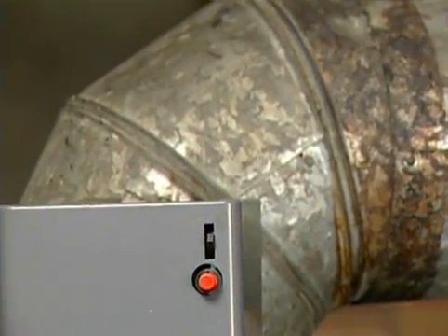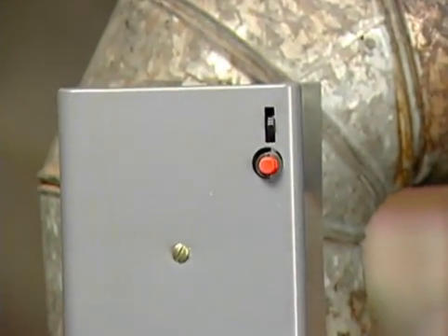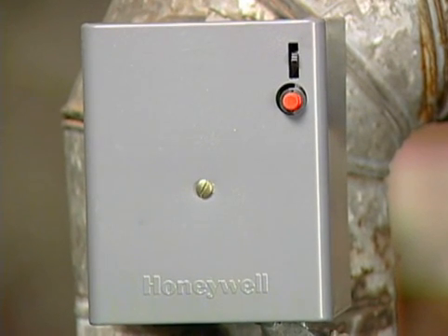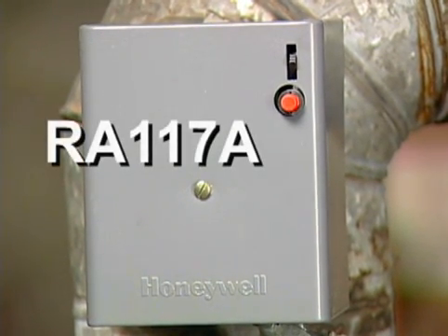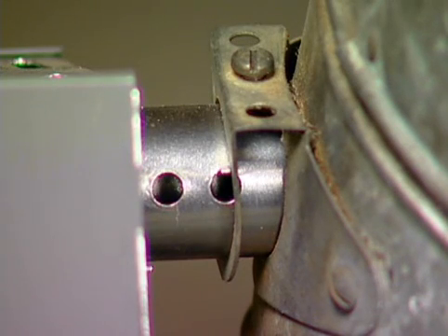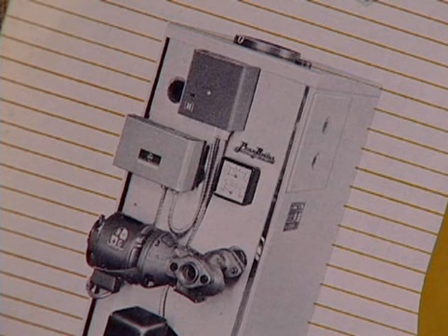For the next few minutes, we'll examine the most commonly found thermomechanical primary controls still in operation today, the Honeywell RA 117A. The RA 117A is typically mounted in the flue pipe, although you may occasionally find one mounted directly into the flue collector or elsewhere on the heating unit.